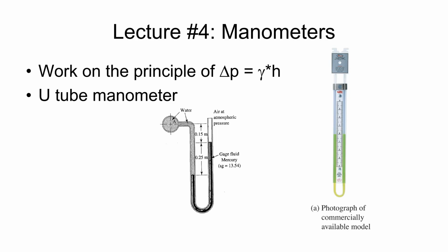And typically these are elongated tubing that are filled with a fluid. Nowadays, a lot of times it's an oil or water that's had a dye added to it. In the past, you would also see ones with mercury inside of them. For the one image, we have an example of a U-tube manometer from Dwyer. On there, you can see a yellowish color.